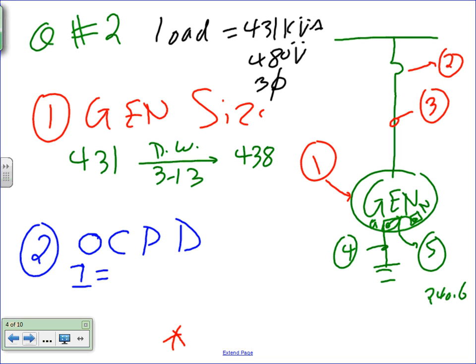438, the next standard kVA, typically. Now, that's for the test. In real life, you're going to use the common software that I gave you guys. You're going to grab the size from the software based on the loads that you have. And the kVA, basically, step number one, and I hate to say it, step number one will be done by software for you.